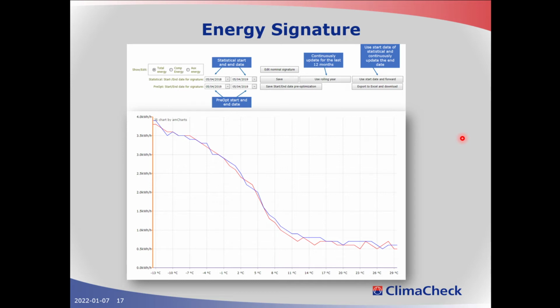So you can enter a schedule for a measurement, typically office hours or opening hours for a store, and then the server will divide the energy consumed over a high load and low load period, and that is what we are looking at here with the blue and the red line. For this system here, there is basically no difference between high and low load periods, but typically for a store you would see a bigger difference here.